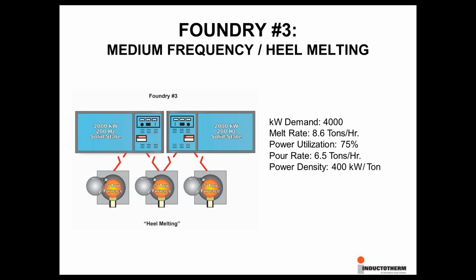Foundry number 3 is operating at a total kilowatt demand of 4,000 with a melt rate of 8.6 tons per hour. Using a power utilization of 75%, they're able to achieve a pour rate of 6.5 tons per hour. In this case, the power density is 400 kilowatts per ton, which is substantially higher, as shown in the previous examples. As a result, we have now reduced the kilowatt of demand to 4,000 kilowatts, yet we are still maintaining a pour rate of 6.5 tons per hour.